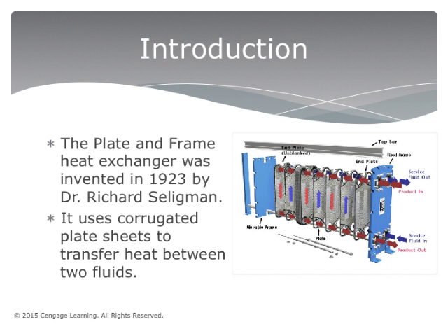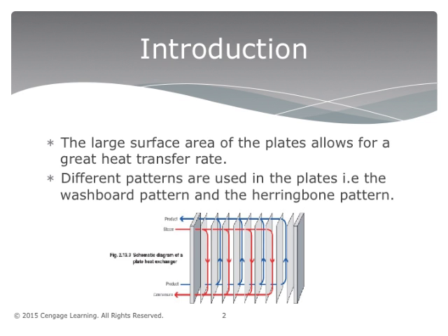The advantage of this over a conventional heat exchanger is that the fluids are in contact with the larger surface area of the plates. This allows for a much greater transfer of heat, therefore increasing the rate of the fluid's change in temperature. Different patterns are used in the plates, such as the washboard and the herringbone pattern. In the herringbone pattern, the angle made between the adjacent ribs and the vertical ribs is called the chevron angle, theta. Plates can be made with small chevron angles, low theta plates, or large angles, high theta plates.